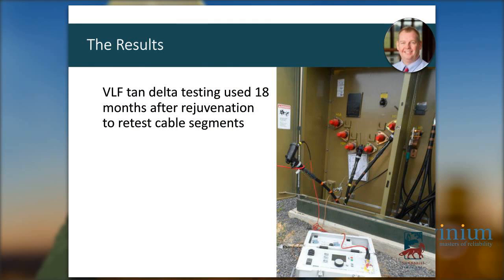One of Steve's strengths in terms of diagnostics, and in selling this to both me and the City Council, is the use of tan delta and power factor testing on this cable beforehand—and then we had him go back afterwards. Steve went back at 6-month intervals after injection on the spans originally targeted as test spans, and he ran VLF tan delta tests for 15 minutes at 6 months, 12 months, and 18 months.